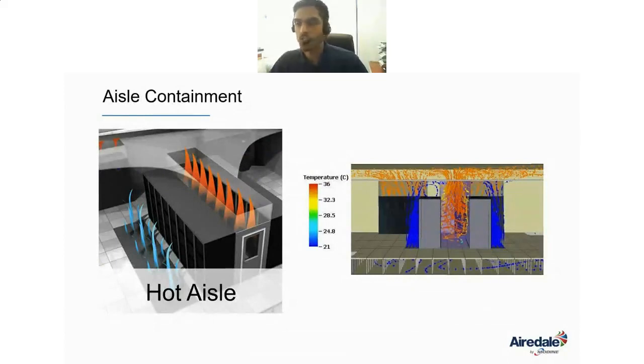Aisle containment is one of the most important recent developments. In the beginning, when hot or cold aisles were invented, they were not properly oriented and there was still a lot of mixing of air due to inefficiencies, so air entering the server was 2 to 5 degrees lesser than outside.